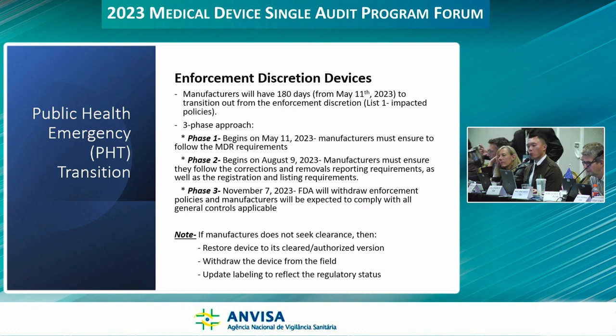So one note on the bottom, I think that's pretty important. If a manufacturer does not want to seek clearance, then they need to restore their device to its cleared authorized version, withdraw the device from the field, and update labeling to reflect the regulatory status.